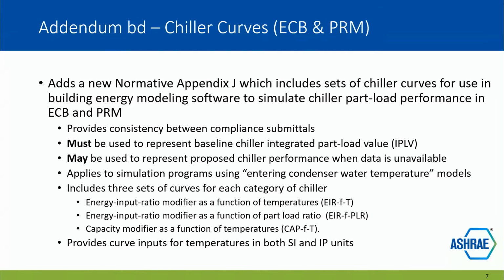And those curves are optional in your proposed building design because you can often go to a manufacturer and get the exact part load performance curves for that chiller. But if they're not available, these curves provide a default. But in the baseline, they're required. Since the baseline is not based on a particular piece of equipment, just on an IPLV rating, you now have to use these part load performance curves in your baseline design. And the curves are provided in both SI and IP units, so they're usable in a variety of simulation programs.